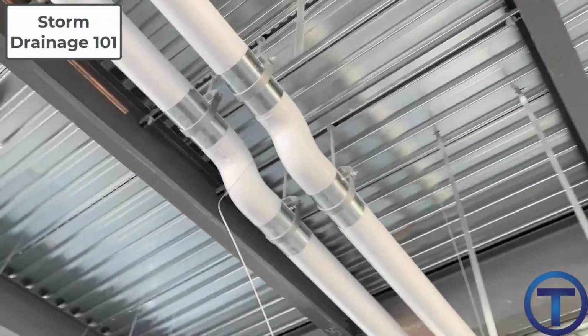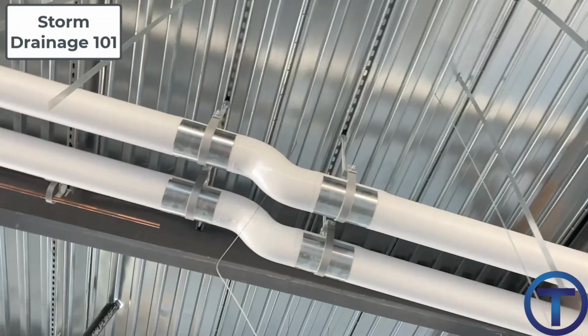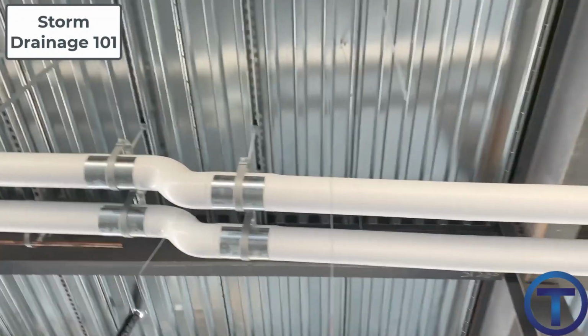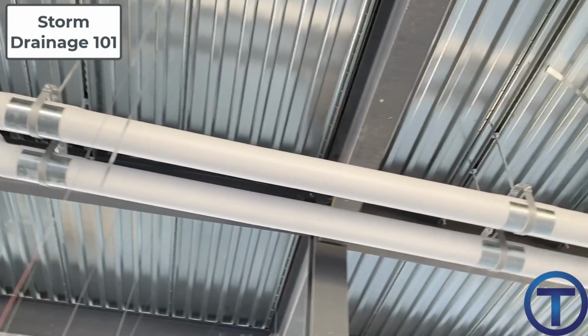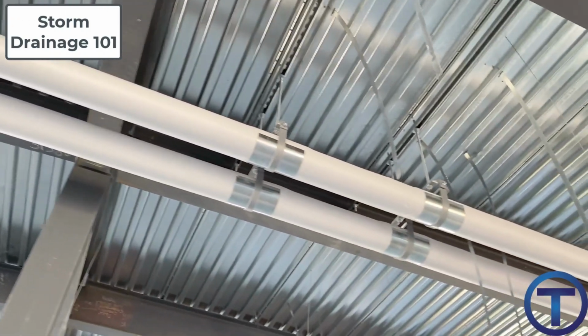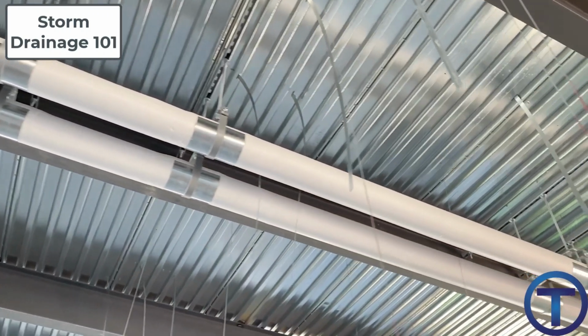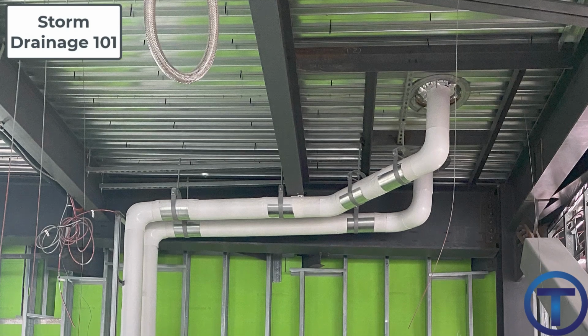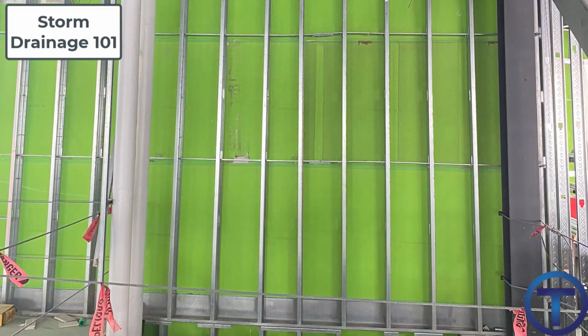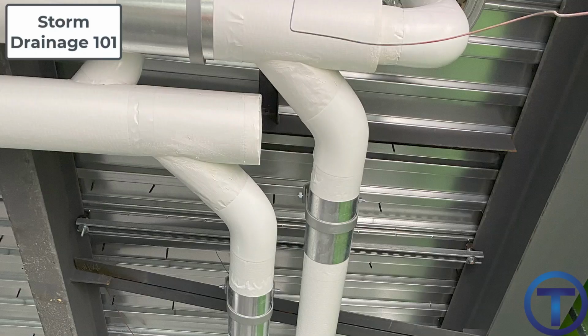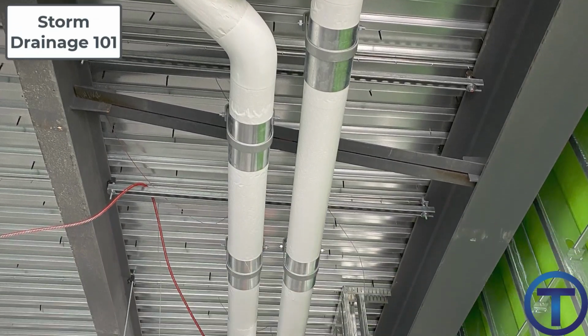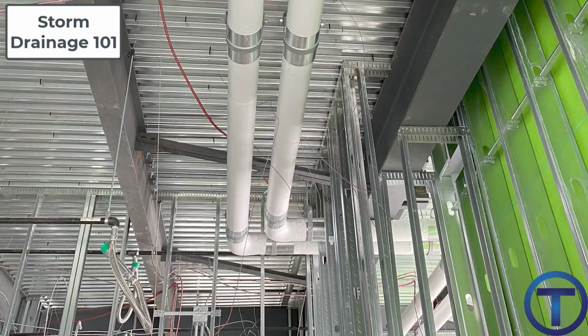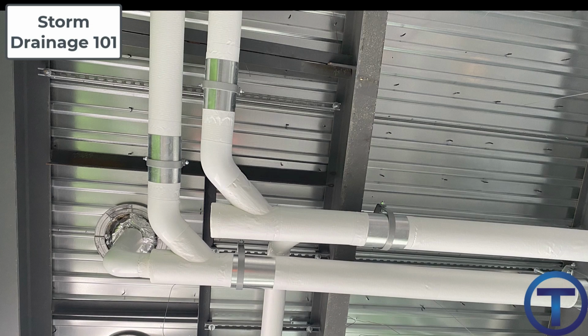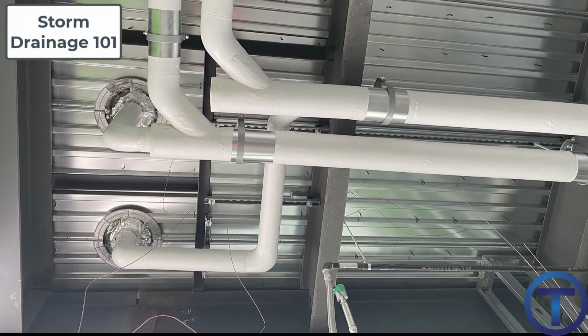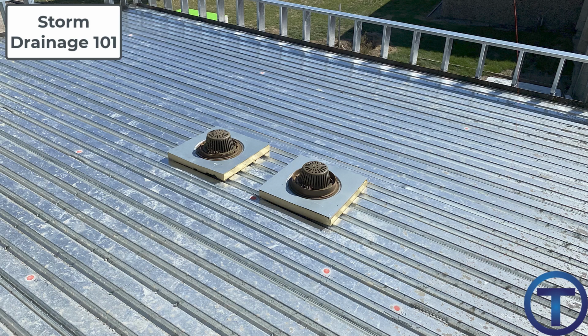If you're inside of a heated building and there's any moisture at all in the air or humidity, and you're dealing with water that's coming from the outside, so that rainwater or even melting snow is going to come in and it's going to be very cold. The pipe will be cold. And a cold pipe exposed to humidity or moisture in the air is going to create condensation. The water will collect on that cold pipe and it will start to drip. So the insulation is actually going to protect the inside of the building from condensation and water damage that can happen because of condensation.